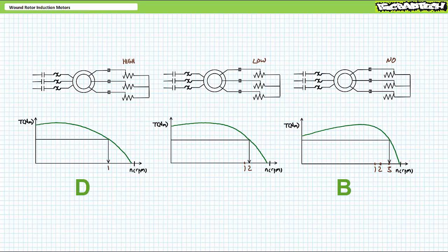Alternatively, one could flip this application on its head and try to keep speed constant given variable torque by varying rotor resistance. In summary, by continuously varying rotor resistance up or down, an operator could get a particular load torque to span a desired rotational speed, or attempt to maintain speed constant given variable torque. However, every time you add rotor resistance, inefficiencies creep into the system. It is for this reason that inexpensive motor drives have largely supplanted this technique, although you might find it still used on occasion.